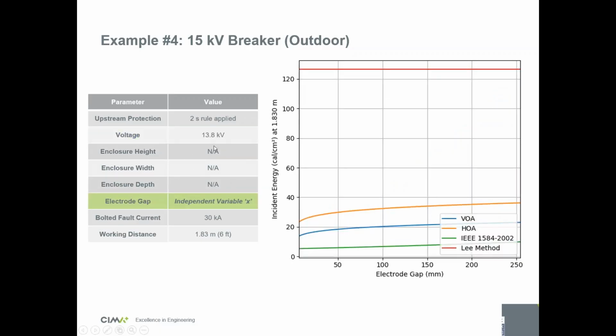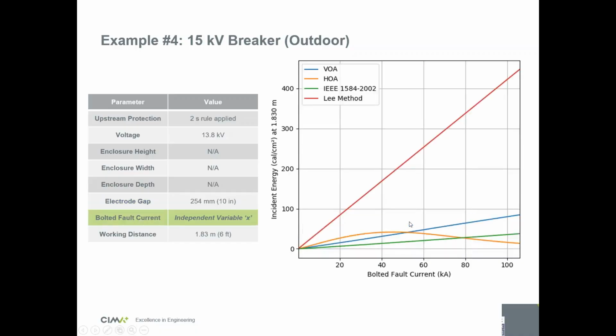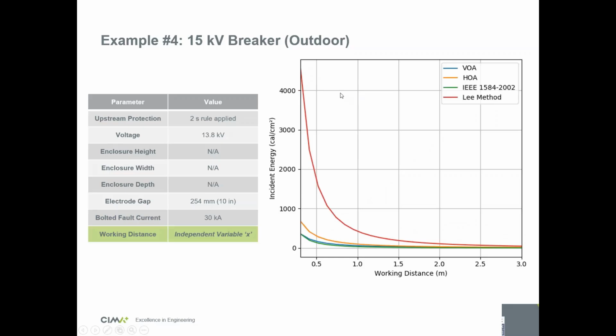So if you plot it against... in this case, there's no enclosure height, width, or depth because you're in open air, so there's no box. Here you can see the electrode gap has no impact on the Lee method because it's not a parameter, and you don't see much variation with the electrode gap in the old equations. Bolted fault current, you see the Lee method basically is a 45-degree angle that goes up to 400 calories. But the old and the new method are basically in the same range. And then the working distance, well, it's the same. So the Lee method goes up to 4,000 calories in that case, if you're really close to the arc.